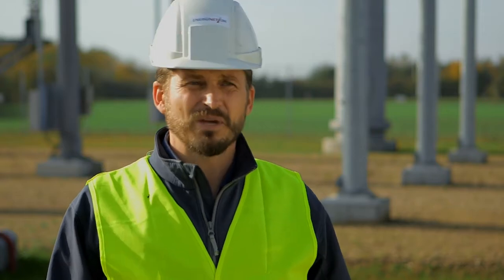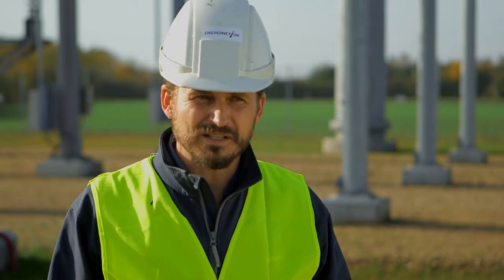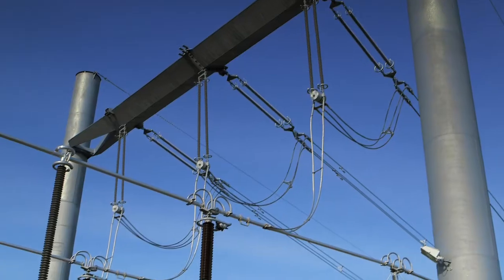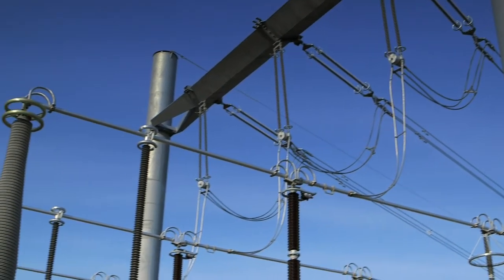Basically, it's a blocking scheme we have here. If we have a fault on one of the parallel cables, we send a blocking signal to both ends. We actually inhibit the auto-reclosure scheme.